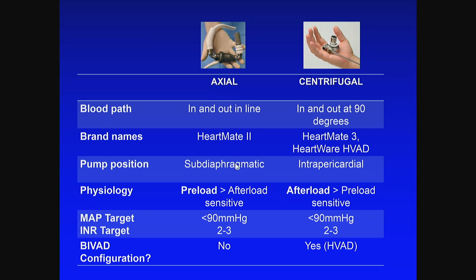The axial flow pumps and the earlier pulsatile pumps I was showing you are subdiaphragmatic implants, whereas the centrifugal pumps are small enough that they can be intrapericardial implants. Axial flow pumps are much more preload sensitive, whereas centrifugal flow pumps are much more afterload sensitive. Blood pressure control is critical for optimal use of centrifugal flow pumps.